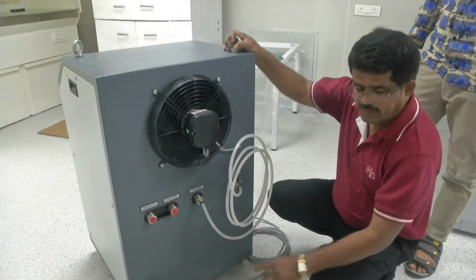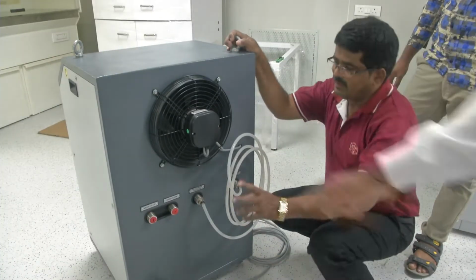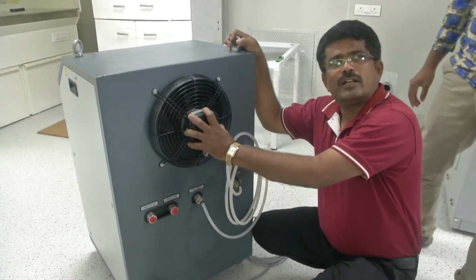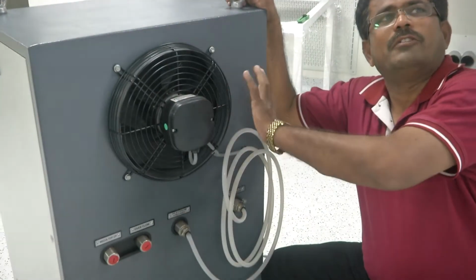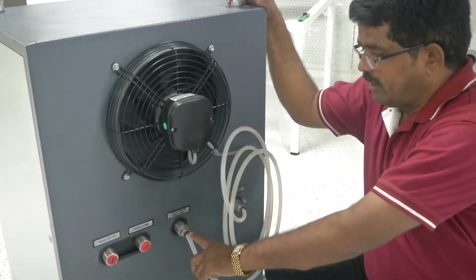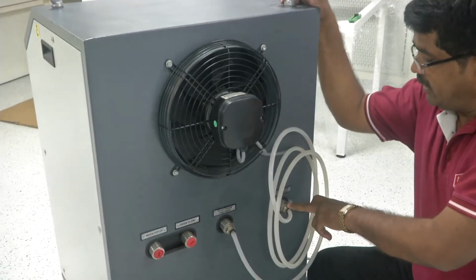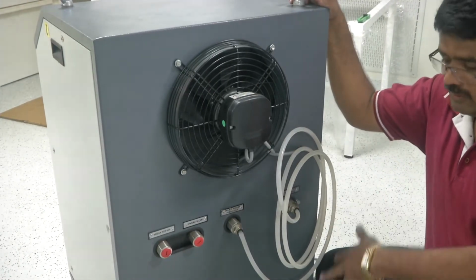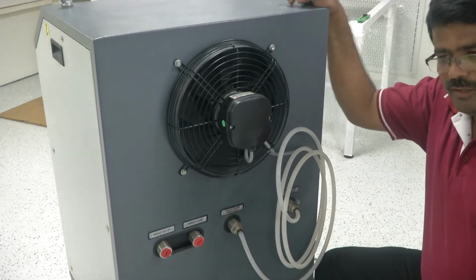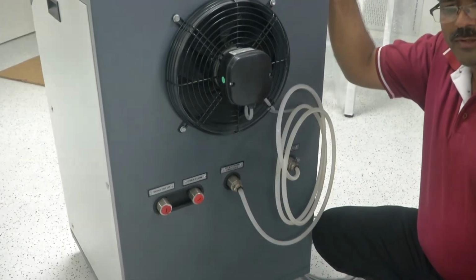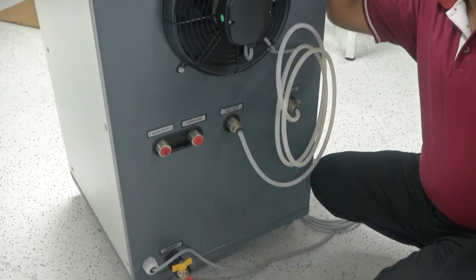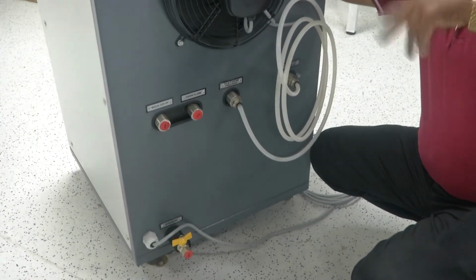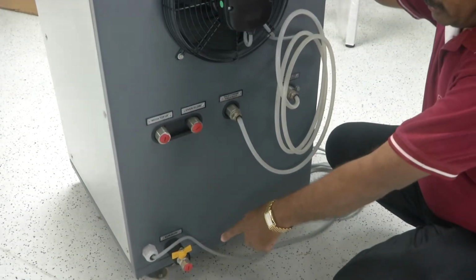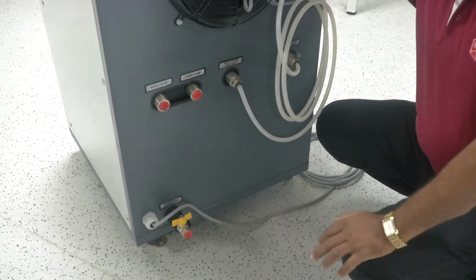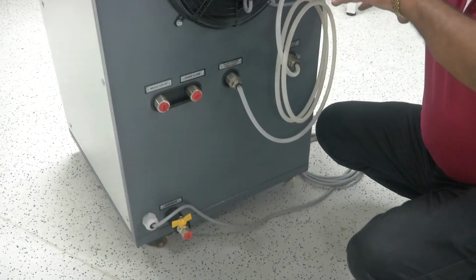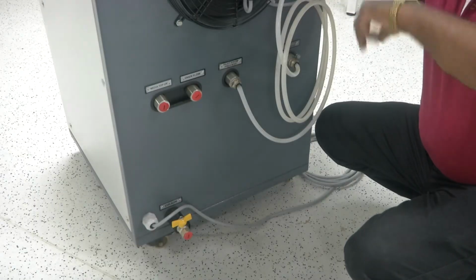Sir, can you tell from first? This is a fan for water cooling purpose. This is the water outlet from the chiller unit and the water inlet to the chiller unit. Once you fill the water, you can run the same water for minimum 3 to 4 months. After water contamination, you can drain the water through this drain valve, clean the tank and refill fresh water.